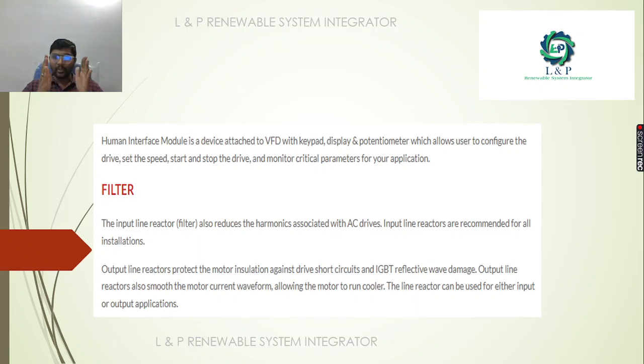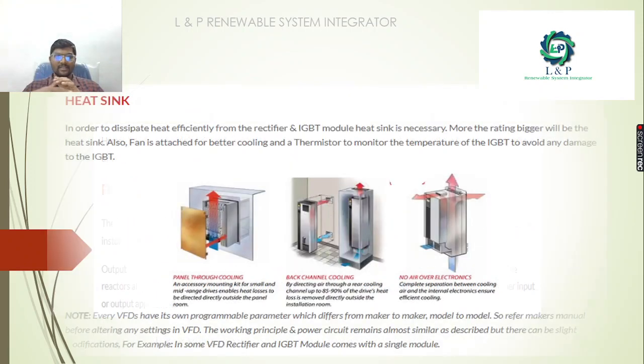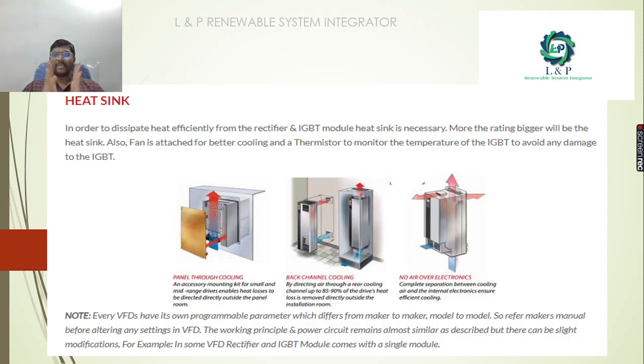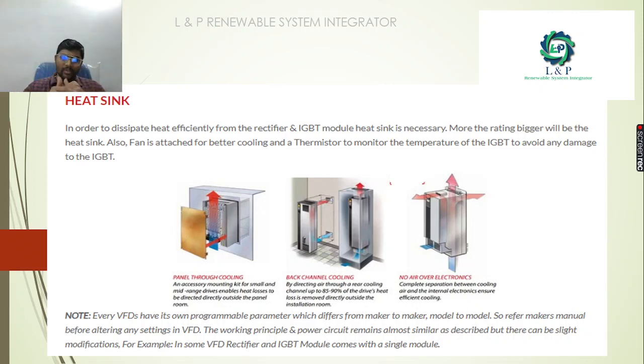Next is the filter. The input line reactor reduces the harmonics associated with the AC drives — that is the important function of these filters. In most installations, we recommend using these filters. And the heat sink — its main usage is to dissipate heat efficiently from the rectifiers and from the IGBT modules. For those two electronic components, we often use these heat sinks. We have back channel cooling, no-air-over-electronics cooling, and panel-through cooling. For cooling purposes, we normally use fans.